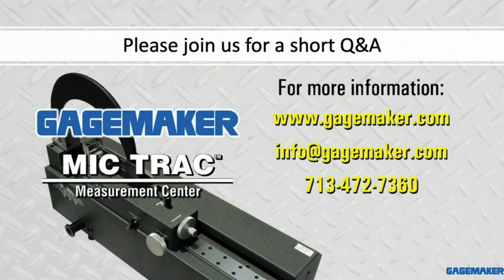What is the standard accuracy needed to calibrate hand gauges? A good rule of thumb is, whatever the hand gauge's accuracy and resolution, let's for example use a dial indicator that has 1/1000th graduation. A typical rule of thumb is you'd like to be 5 to 10 times more accurate with your traceable setting calibration device than the instrument you're trying to calibrate. So if I was trying to calibrate a dial indicator with 1/1000th of an inch accuracy, I'd want my MicTrac to have at least 1/10,000th, or 50 millionths accuracy. If you want to get even higher, 20 times.